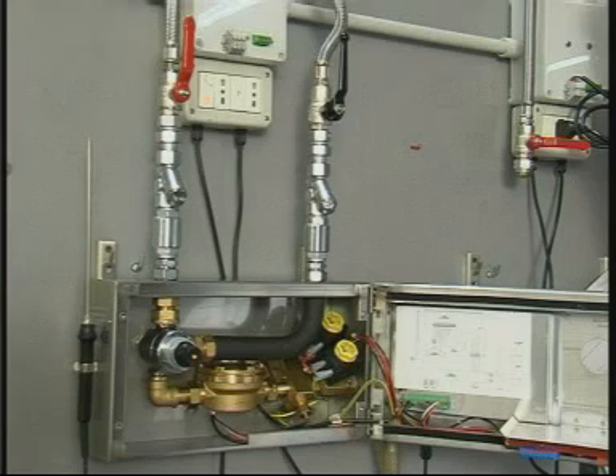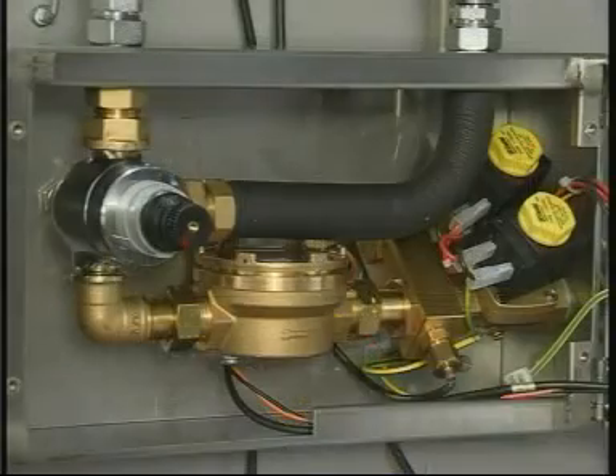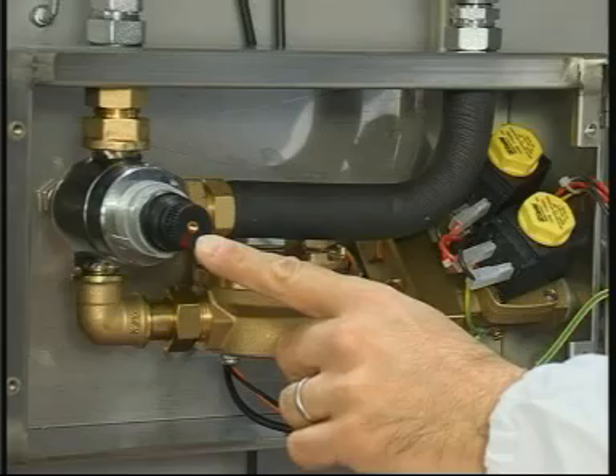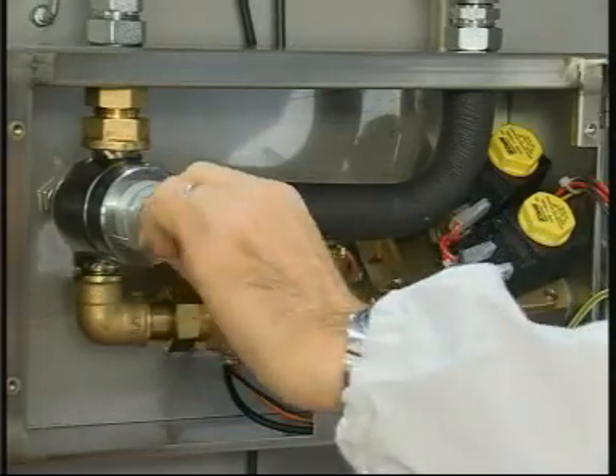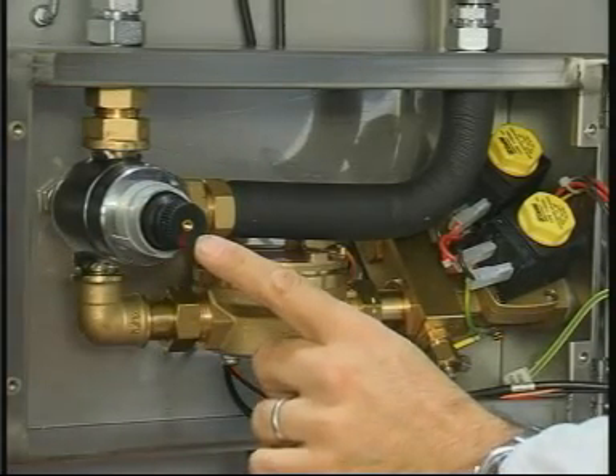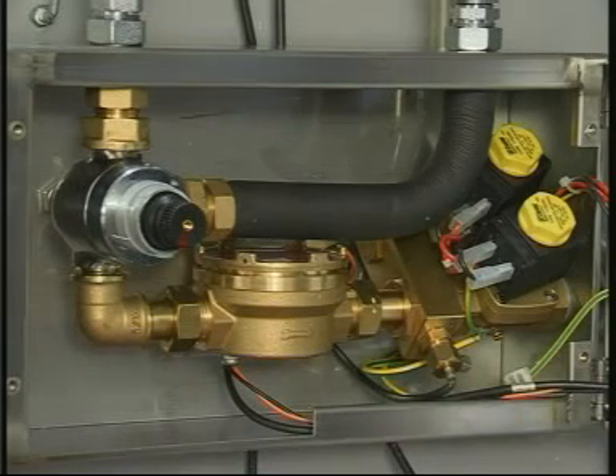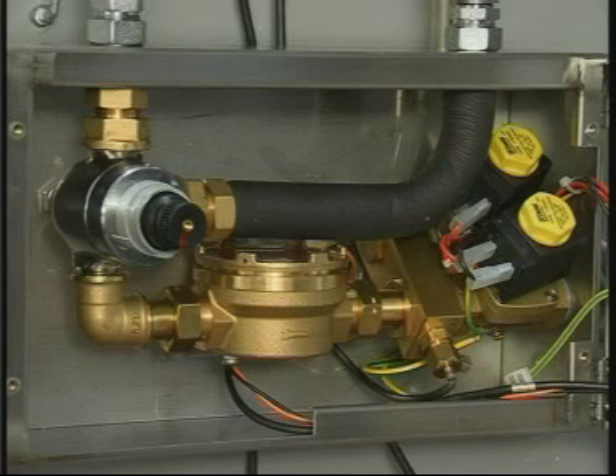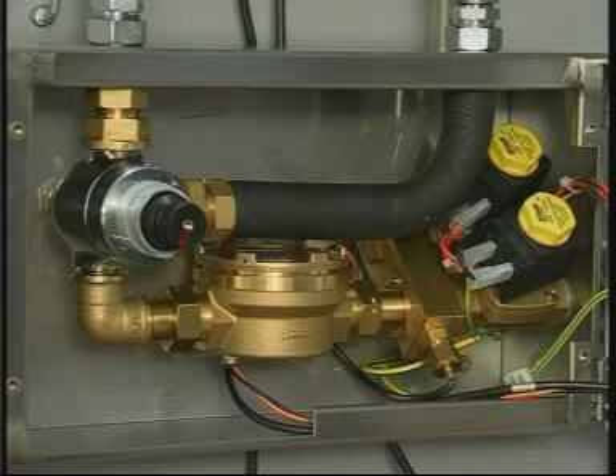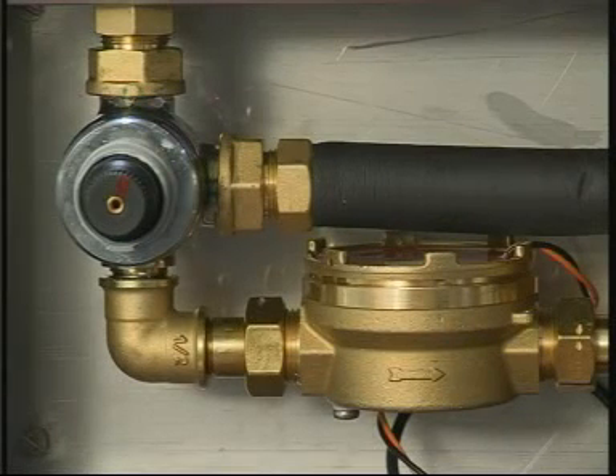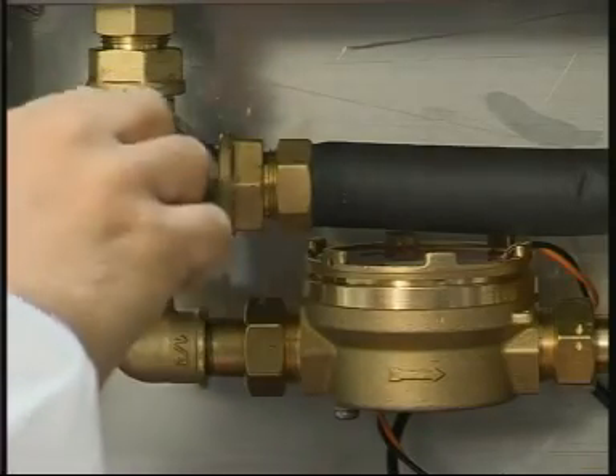Furthermore, verify that the ratio between the pressures at the two inlets is at minimum 1:1 and at maximum 1:5. To carry out the control, bring the knob first to the maximum cold end of stroke and then to the maximum hot end of stroke and read the relevant temperatures on the display. If the temperatures and the pressures at the inlets are correct, but it is not possible to regulate the temperature, replace the thermostatic element. Close the water inlet ball gates and release the pressure by pressing start and, after few seconds, stop. Switch off the supply to the machine.